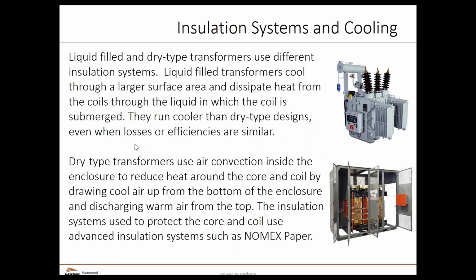A lot of times you run into questions on the insulation system, and by their very nature, liquid-filled transformers run cooler, and they have to run cooler because of the insulation system that they use. And they have some methods to cool themselves differently than a dry-type transformer does. However, the insulation systems for a dry-type transformer are much, much more robust. So really, when we talk about the temperature rise, what temperature that transformer runs at, you do not need to have an equivalent, very ultra-low temperature rise for the dry-type. The insulation system can handle much higher temperatures and still give you easily the equivalent lifetime of use that an oil does. So, we do not have to change and make sure that the temperature rise requests are equivalent.